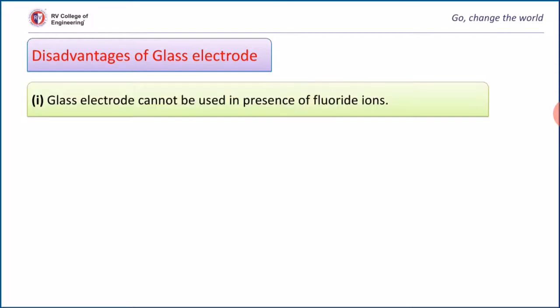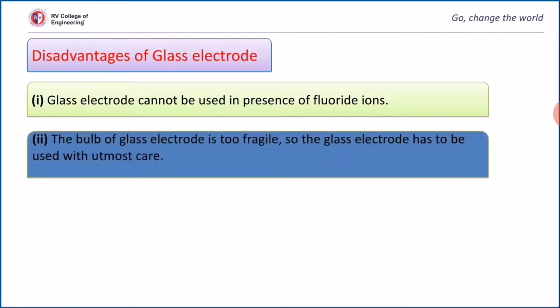Let us see a few disadvantages of glass electrodes. This glass electrode cannot be used in presence of fluoride as it attacks the glass membrane. The bulb of the glass membrane is very small thickness, 0.01 mm to 0.03 mm, and is very delicate to handle.